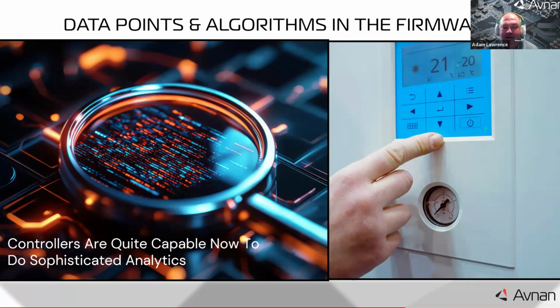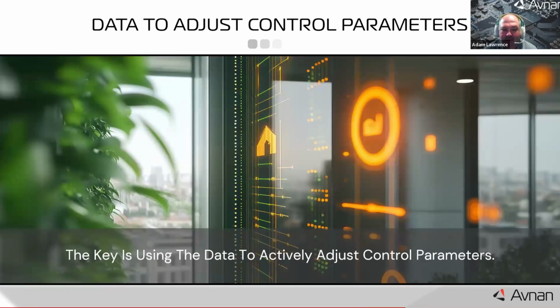Modern HVAC controllers can read a variety of sensors: temperature, pressure, humidity, indoor air quality, and electrical measurements. All these data points feed into algorithms in the firmware. Some algorithms might be simple threshold-based logic. If the coil delta temperature is low and the compressor is at full speed for a long time, flag low performance. Others can be more complex, such as model-based or machine learning algorithms that learn the system's normal signatures and detect anomalies. Some advanced controllers implement performance maps or AI models to continuously compare expected versus actual performance. While full AI might be in the cloud domain, local controllers are quite capable now to do these sophisticated analytics. But even without AI, you can cover a lot with physics-based logic and statistical triggers.